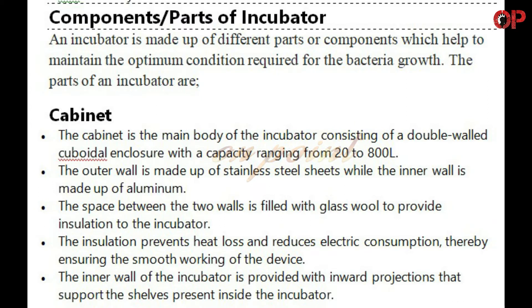Components: An incubator is made up of different parts or components which help to maintain the optimum condition required for the bacteria's growth. Cabinet: The cabinet is the main body of the incubator, consisting of a double-walled cuboidal enclosure with a capacity ranging from 20 to 800 liters. The outer wall is made up of stainless steel sheets, while the inner wall is made up of aluminum. The space between the two walls is filled with glass wool to provide insulation to the incubator.